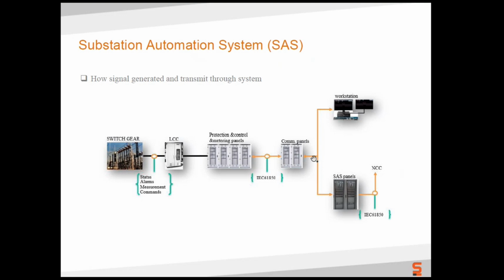Same thing - if you want to send through NCC, it is also sent through this 61850 protocol. So from this communication panel, you can operate locally, in the relay or control room where the operator sits, or from NCC. The NCC operator, the load dispatch center, will send the command to operate this switchgear.